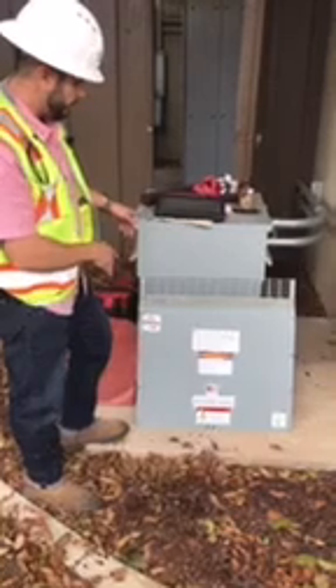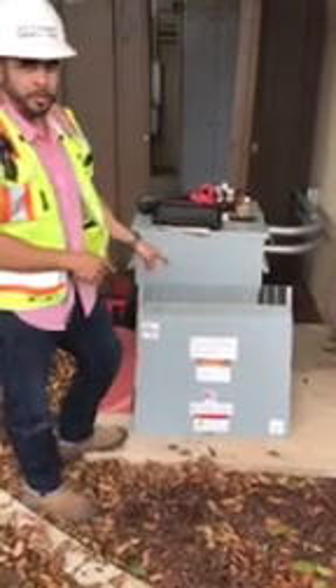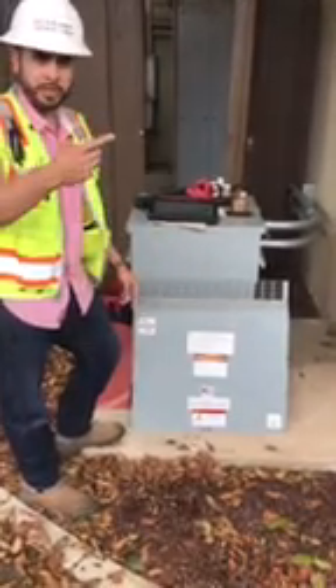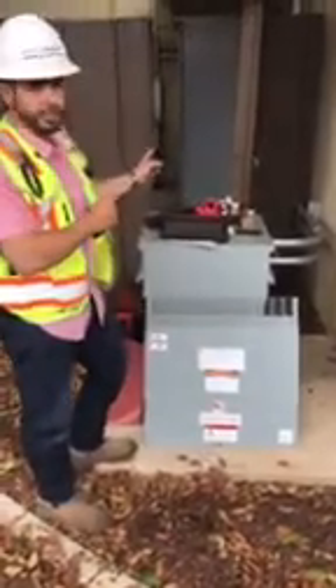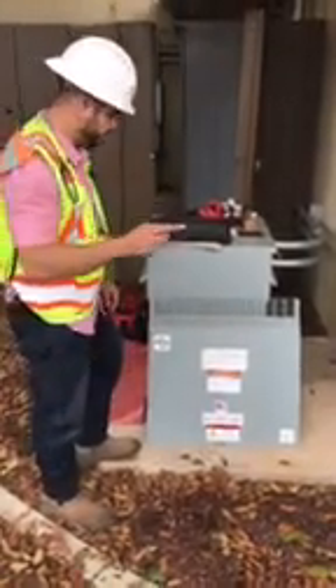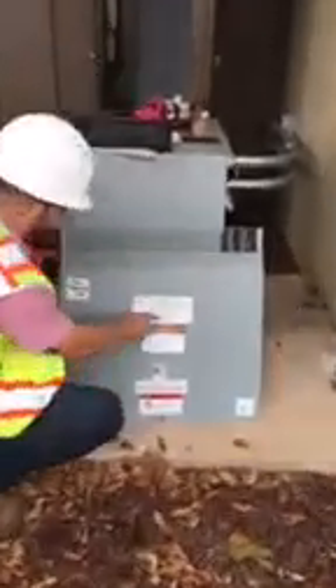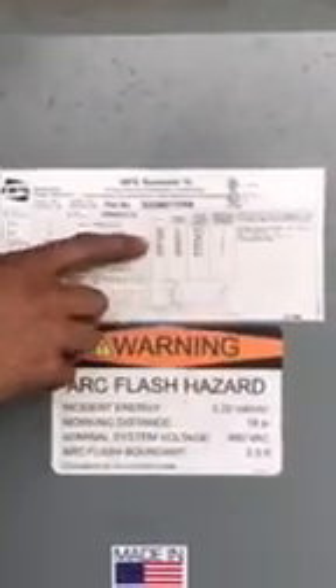So here we have a 208 step-up transformer. So we have a utility grid that's 480, and then it goes to a 208. So I'll show you the tapping coils here. And you can zoom in real quick so you can see it. So this transformer was originally tapped on to what we call tap sequence number 3. And you can see here the grid voltage is 480.